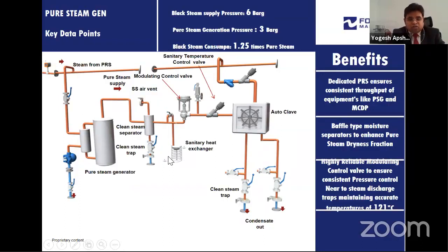Then we also have sanitary heat exchangers where you can do the pure steam sampling. The condensate of the pure steam should comply with the WFI standards, either US Pharmacopoeia or European Pharmacopoeia. In this case, we can validate the quality of the steam. Then we can have modulating control valves for pure steam applications, then sanitary safety valves and sanitary temperature control valves, which go to the autoclaves.